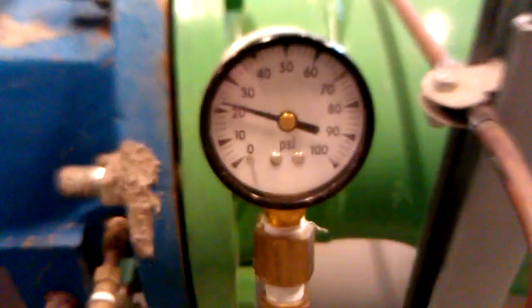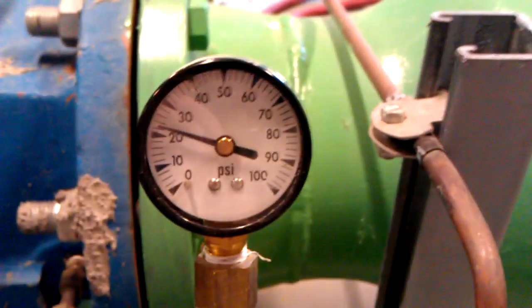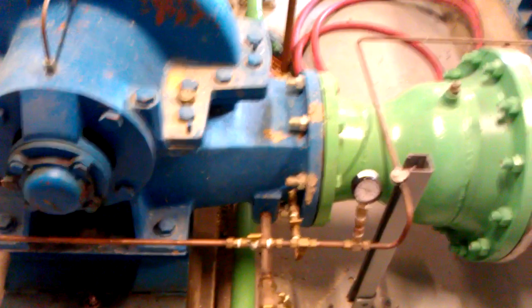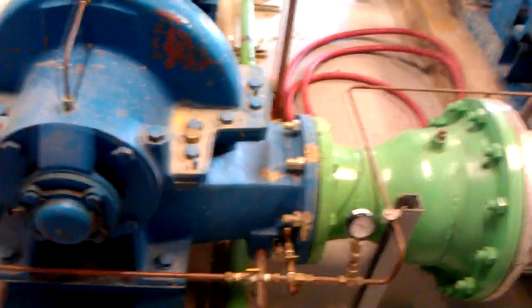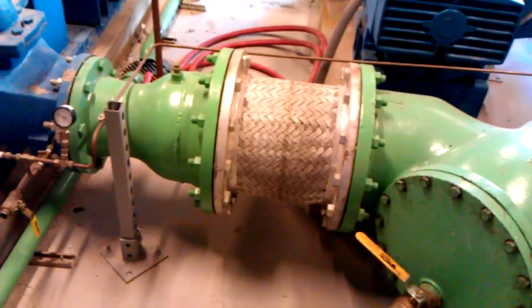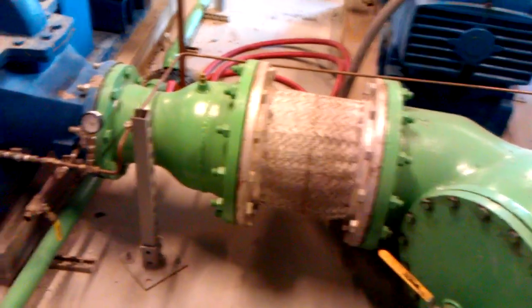Look at that. Water pressure is low. That'd be the discharge pressure on the condenser water pump. It's gonna be time to clean the screens. First I gotta go clean them screens out in the cooling towers. Those are probably the main culprit.